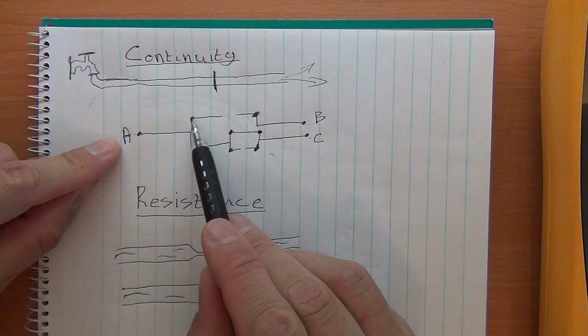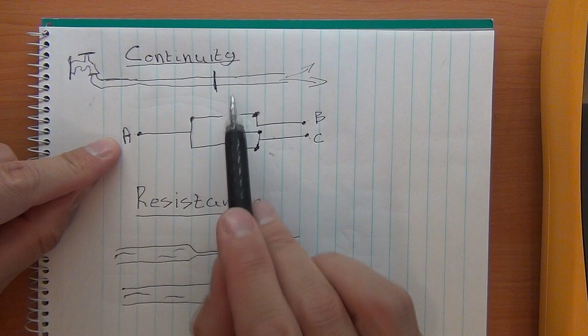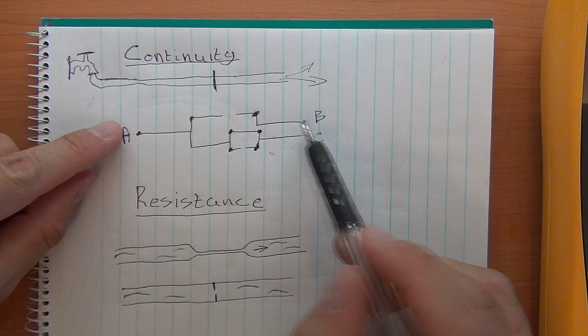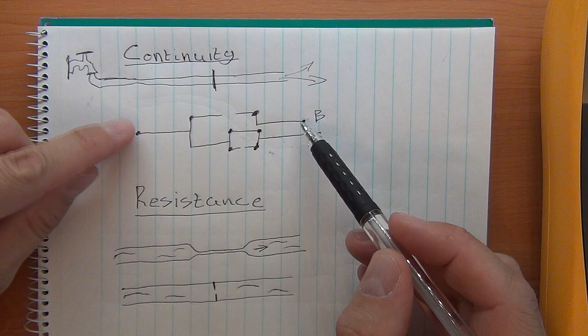If I check between point A and B, have we got a continuous path? No, it's fairly straightforward. We can see we've got a break. So if this was a pipe, we would have water gushing out here. We wouldn't have water coming out at point B where we want it, and that would be a breaking continuity. And with our multimeter, if we put it over here and did the test, which I'm obviously going to demonstrate later, we would not get our beep.